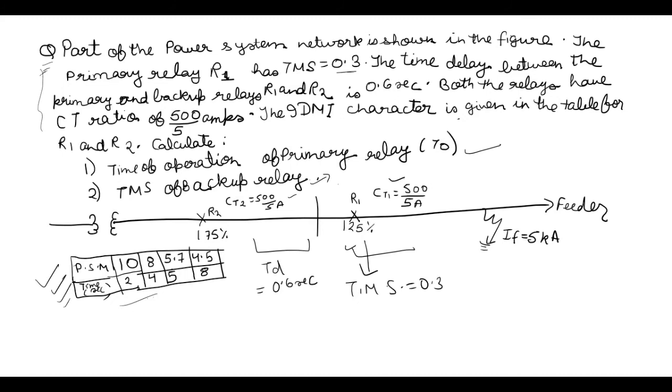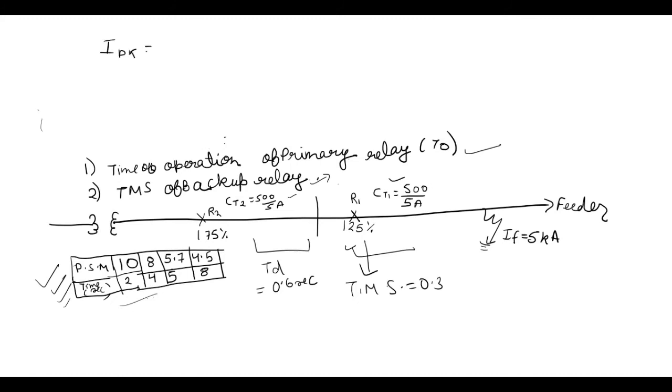So let's start this. So now we will start with the pickup current which was our first formula which is equal to percentage setting of relay. So for R1 percentage setting of relay is 125%, so 125 by 100 into CT secondary current. So by secondary current this means this 5 amperes. So this value is 6.25 amperes. And now the PSM plug setting multiplier, according to the formula it was IF divided by IPK into CT ratio.